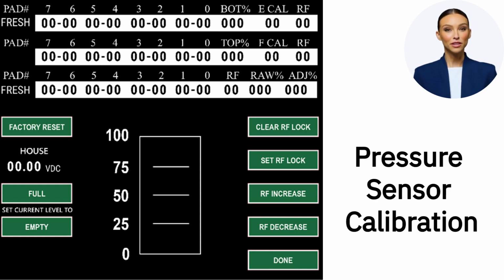Now let's discuss the readings on this screen as they pertain to a pressure sensor. If your coach is equipped with strip sensors, this information is not applicable and will be found in a different video. We will start with the numbers under 1 and 0. These represent a preset reading of Empty. By default, this should show as 1-00 or 100. The numbers under the 5 and 4 represent the preset reading of Full. Typically, this number is between 200 and 300, depending on the height of your particular tank. The numbers under 3 and 2 represent the current sensor reading for the pressure sensor. This number should always be between the empty and full set points.